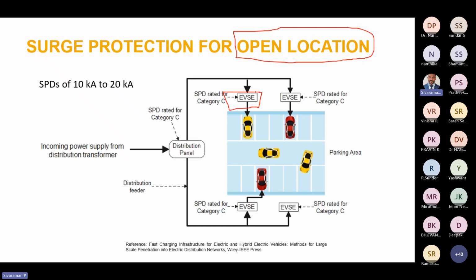In open location, all those equipments are in open premises, so there are higher chances of getting affected by a direct lightning stroke. For those types of locations, we have to use Category C of surge protective device, SPD in short. So for open locations, we have to go for Category C SPD at the main distribution panel.